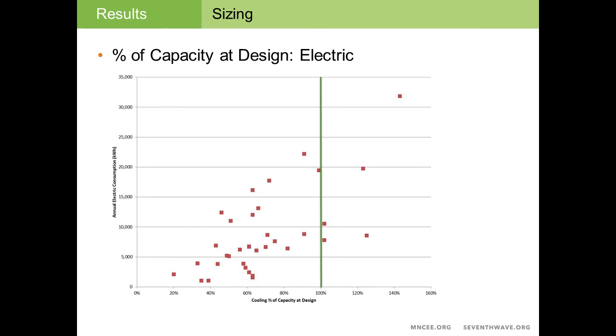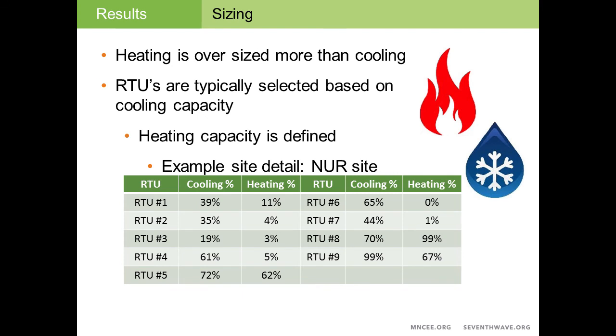These units are much more appropriately sized for the space. We did have a number of units that extended beyond the 100% value, but that was just an anomaly that had to do with the extrapolation of the regression lines from the models and applying the design temperatures. So what we learned is heating is definitely oversized more often than cooling, but that's not a surprise when you start thinking about a rooftop unit.